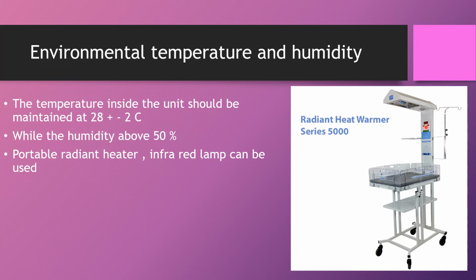Then this is to set the temperature level, mainly 36.5 to 37.5. They have to set the temperature for the baby. Once you have set it, you can feel the temperature. The heat rays will be coming from this light. Based on that, you have to adjust the temperature here. When you keep the palm of your hand in between this place, you can feel the hotness in the air. Based on that, you have to adjust the temperature. The baby requires warmth soon after delivery.